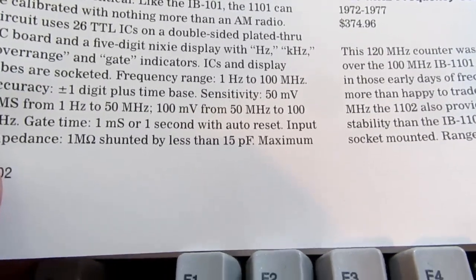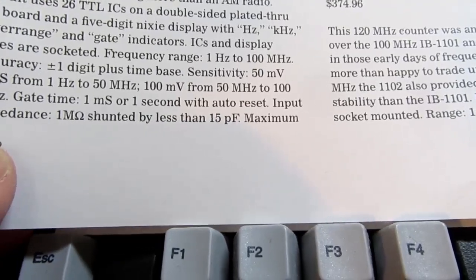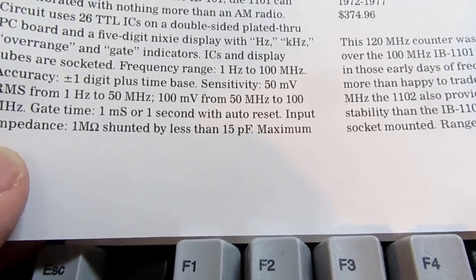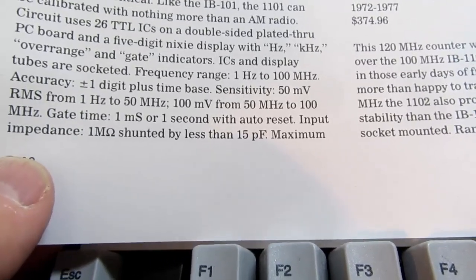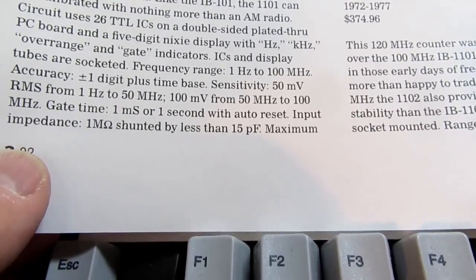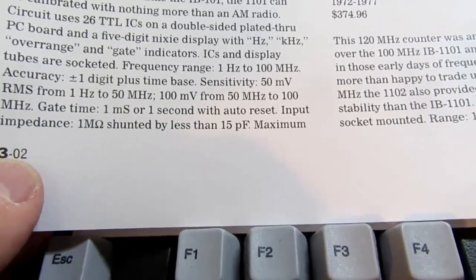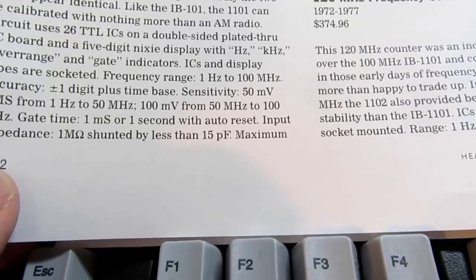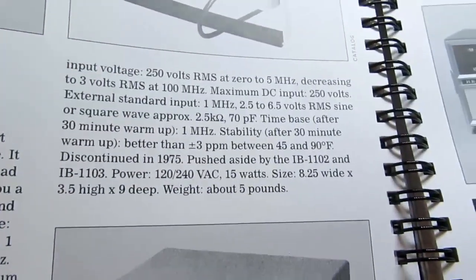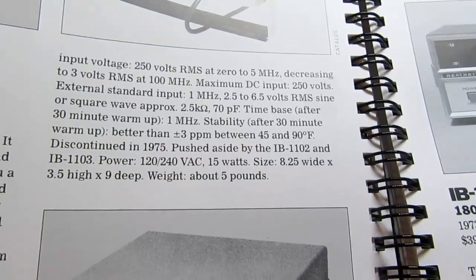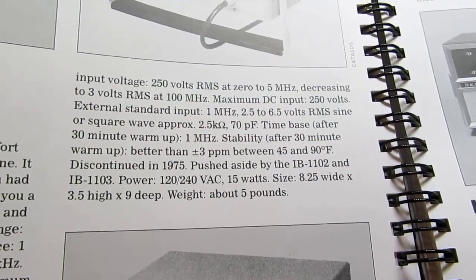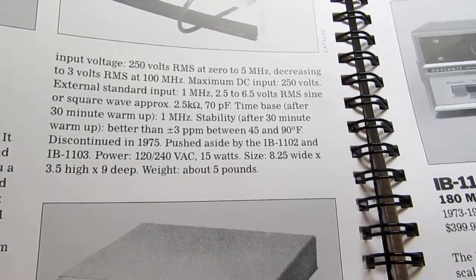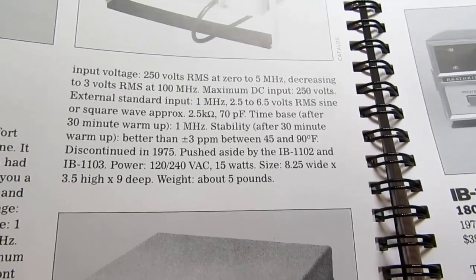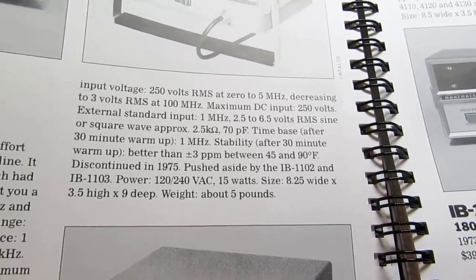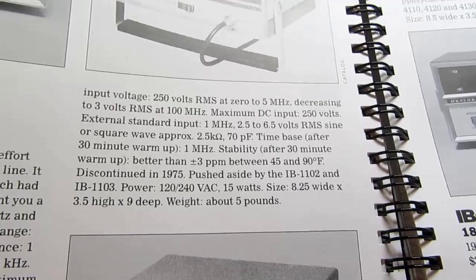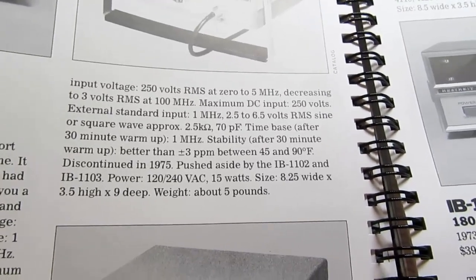Sensitivity as low as 50 millivolts RMS, and as you go up in frequency, the sensitivity is a little bit higher, requiring 100 millivolts. Gate time of 1 millisecond or 1 second with auto reset. Input impedance 1 megaohm shunted by 15 picofarads. Maximum input voltage 250 volts RMS, decreasing to 3 volts RMS as you get up near 100 megahertz. Maximum DC input is 250 volts. It has an external standard input, so you can replace the internal clock with an external clock, perhaps one of known accuracy.